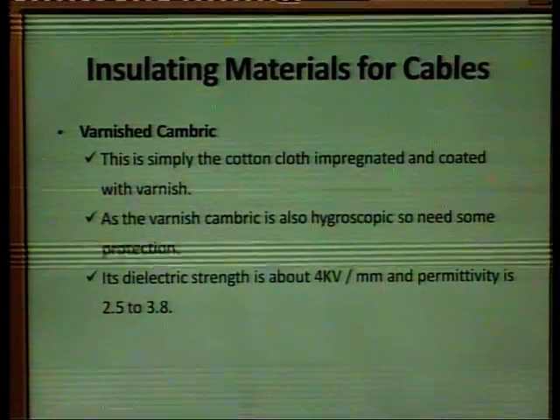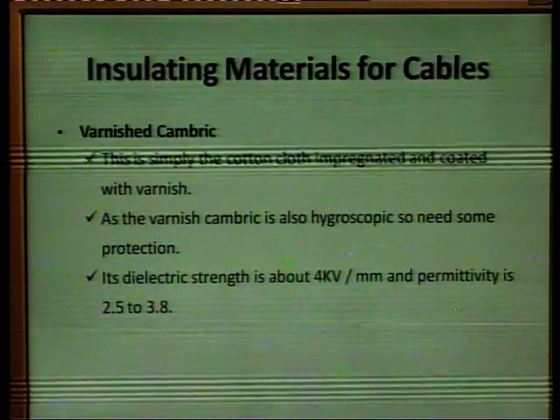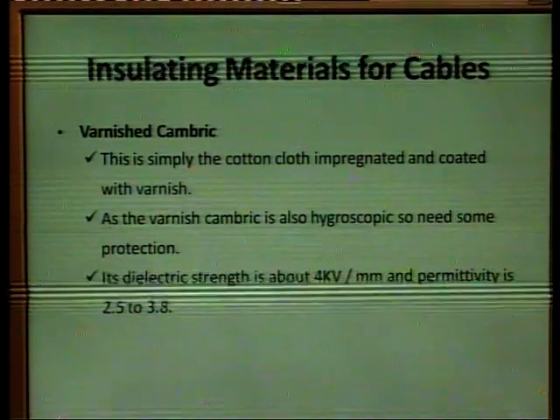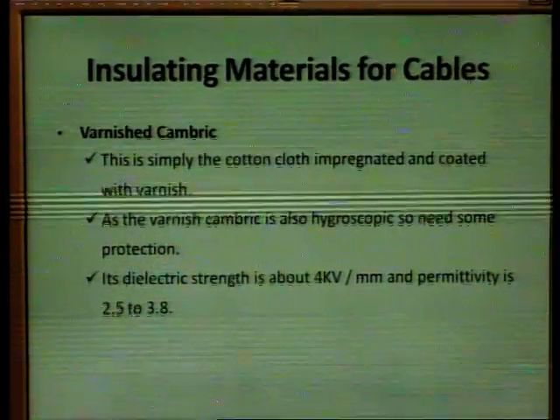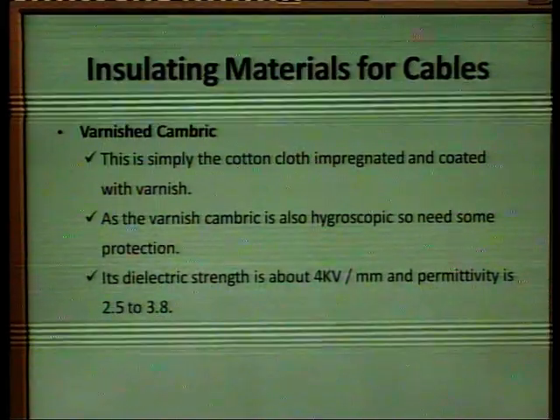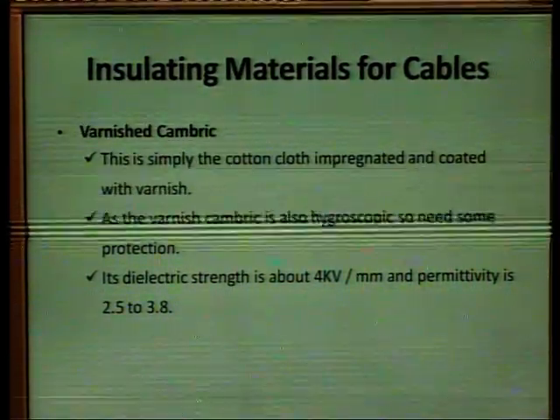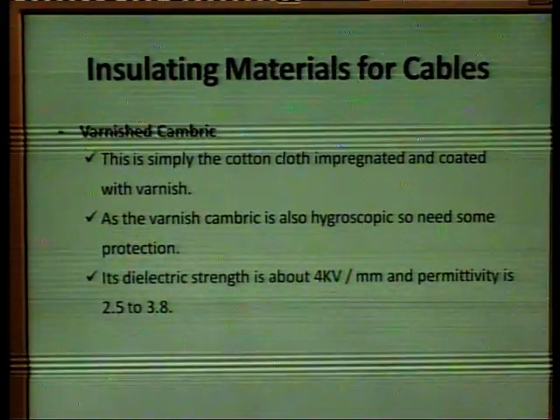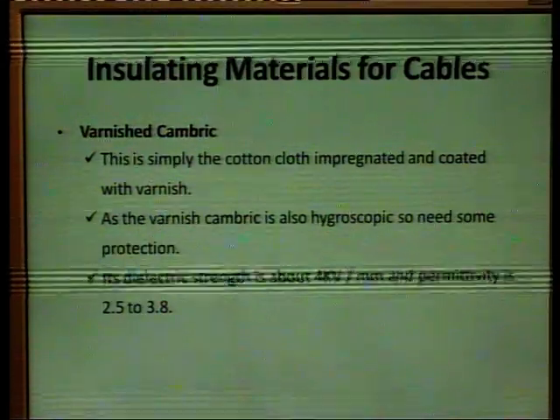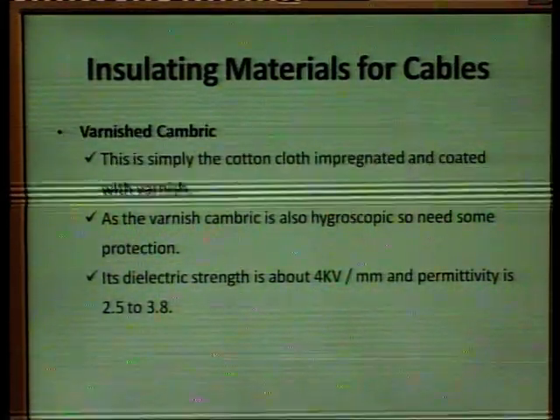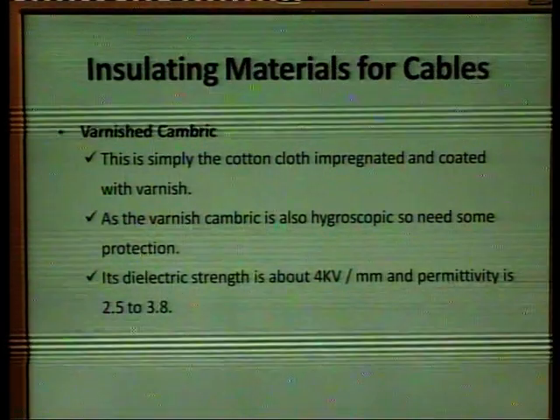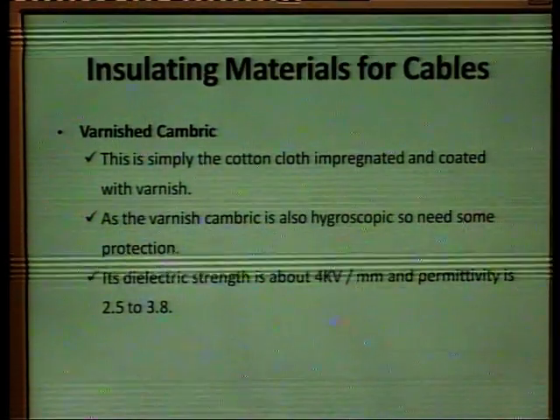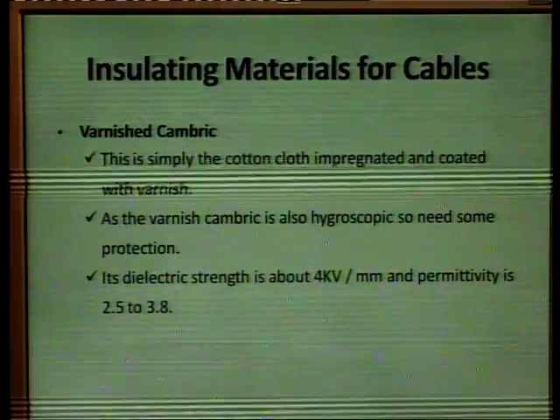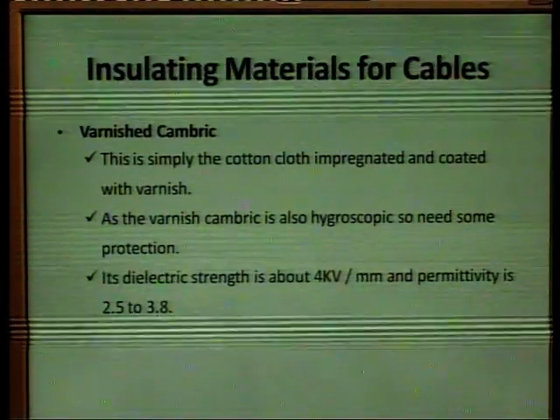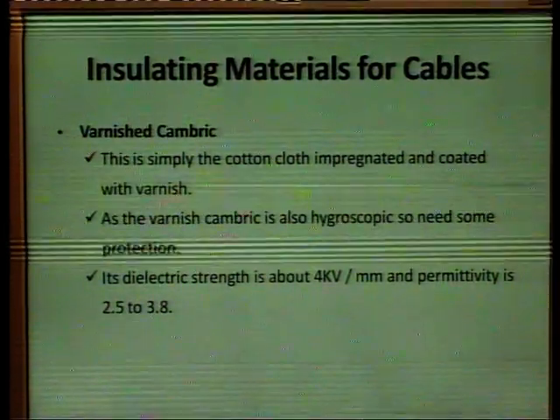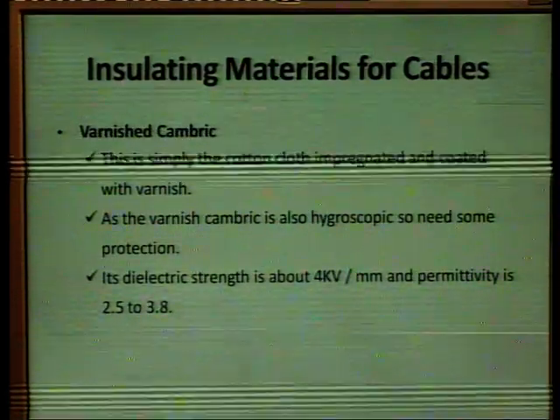Then the next material is varnished cambric. It is a simple cotton cloth which is impregnated and coated with varnish. The varnished cambric is also hygroscopic, and so it needs some protection, as the paper needs. And the dielectric strength of the varnished cambric is about 4 kV per mm, and permittivity is 2.5 to 3.8.